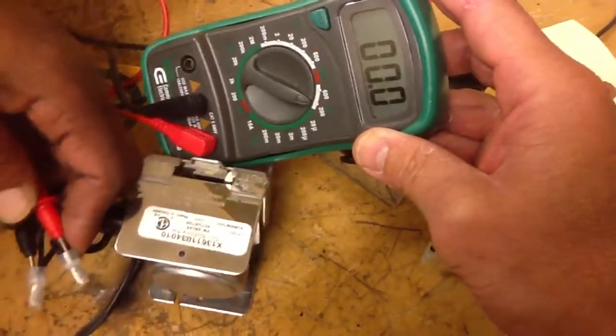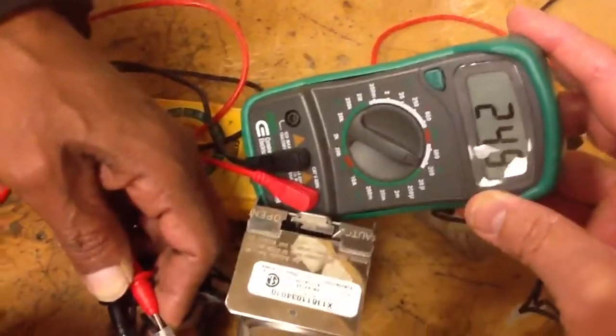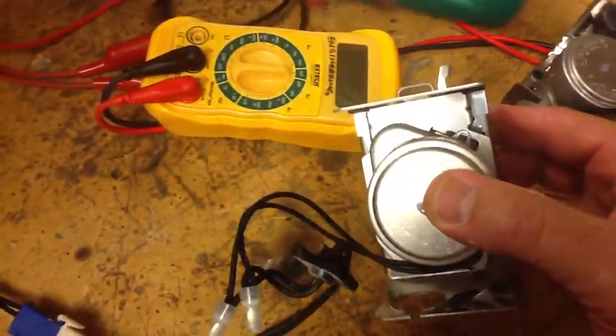You're on there — it's just probably not off. Is it off? Yeah. OK, so you've got voltage. Now there's voltage to it, so you know that the motor itself — which is right here — has voltage, but it's not running.